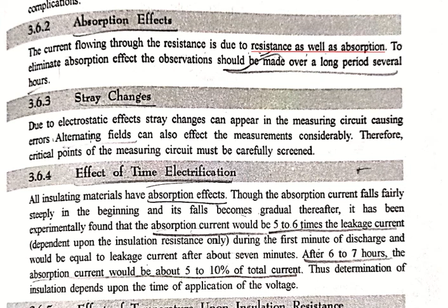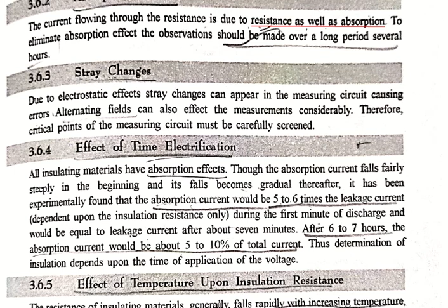Now coming to stray changes. Due to the electrostatic effect, stray charges can appear in the measuring circuit, causing error. Alternating fields can also affect the measurement considerably. Therefore, critical points of the measuring circuit must be carefully screened. We have to keep in mind the electrostatic effects and some stray fields which will affect our current also. So this will also cause error and causes difficulty in the measurement of high resistance.